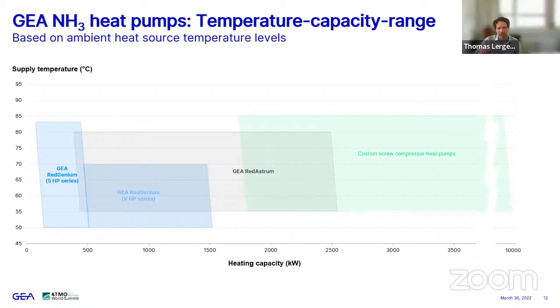I already mentioned that higher supply temperatures means a little bit less available capacity, but the more dominant parameter of your available capacities is your heat source temperature. So this chart here, or this capacity range, is based on ambient heat source temperatures around 30-35 degrees Celsius, or typical temperatures that you see of waste heat from refrigeration plants. So if this heat source temperature drops, let's say you are in a colder region and you are using water from the sea, from the lake, from the fjords, it's often used in the Scandinavic area, then your available capacity becomes significantly less because the temperature drops on the cold side, and that pulls also down your capacity availability range, so to say.